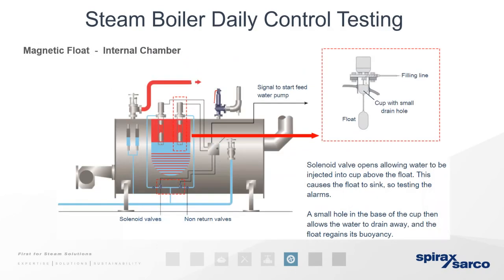Magnetic floats, these again are daily control testing, so you want to make sure these internal ones are still working properly. You need to make sure that they're blowing down properly, that they're controlling, and that you're still getting a signal there. So you'll be manually lowering the level in the boiler to make sure they fire, and so on.